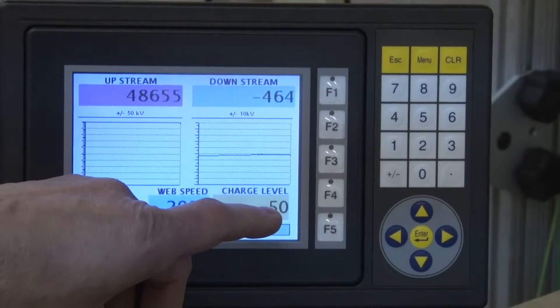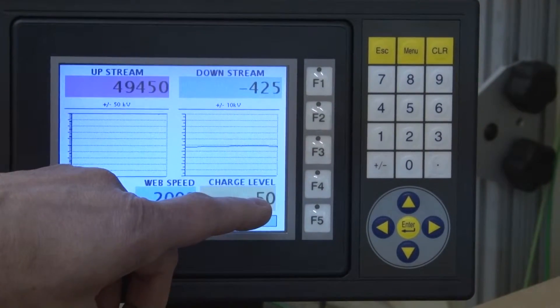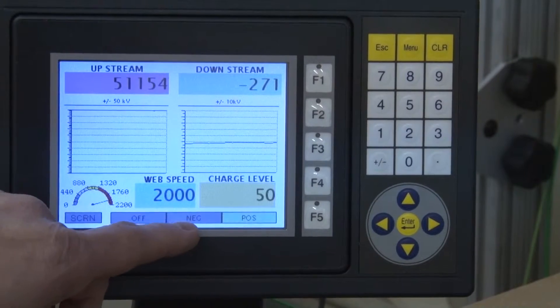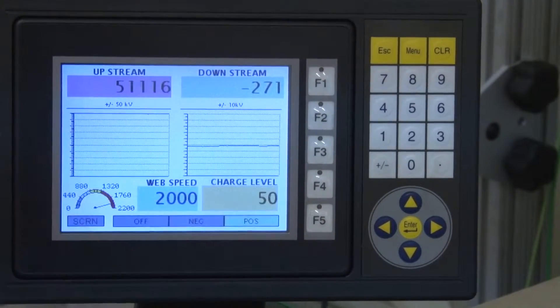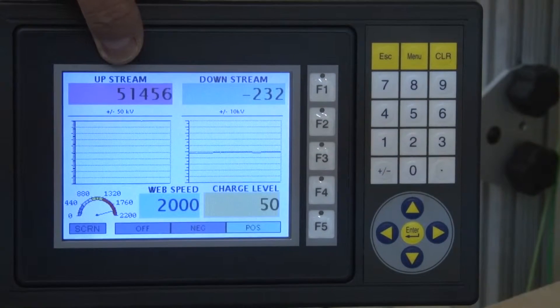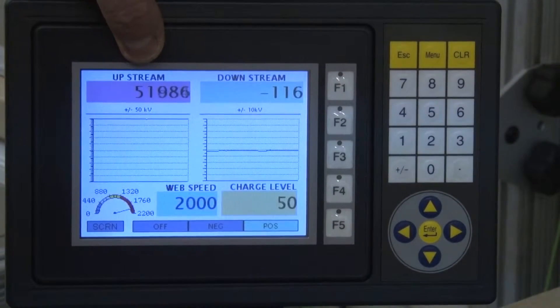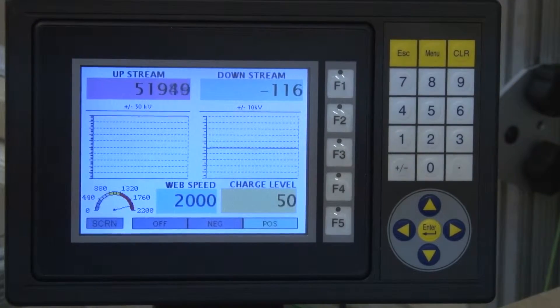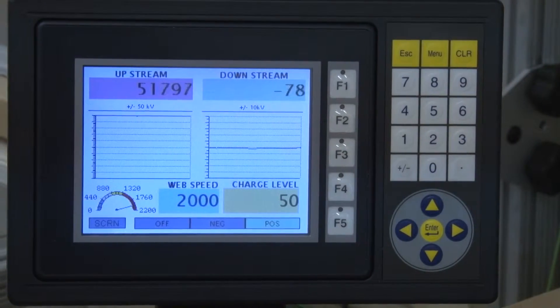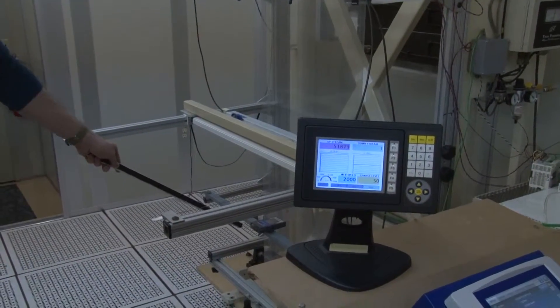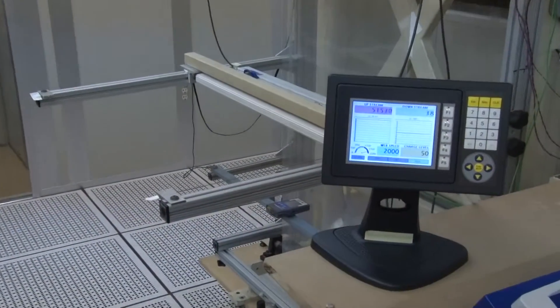We can set the charge level, which is 50,000 volts, and we can set the polarity of the charge, so we have positive 50,000 volts on the web. You can see that our upstream sensor is reading 51,000 volts, so we're making that 50,000 volts on the upstream sensor. So at this point on the material we have 50,000 volts.